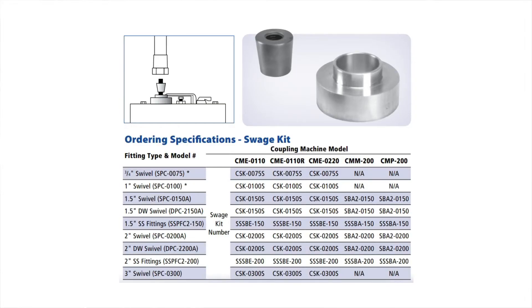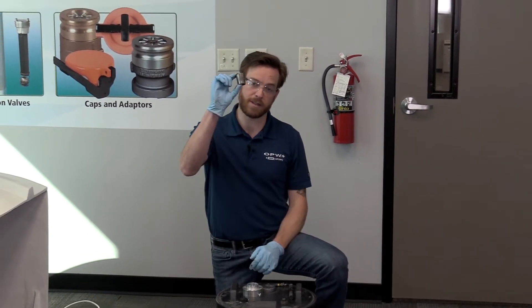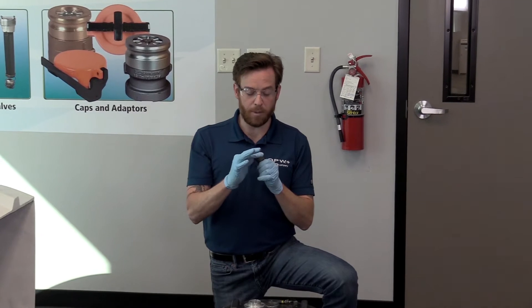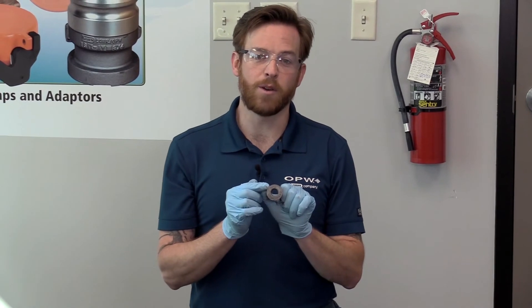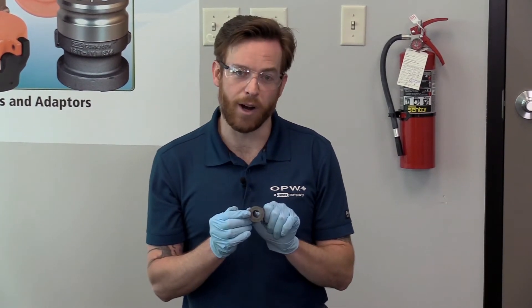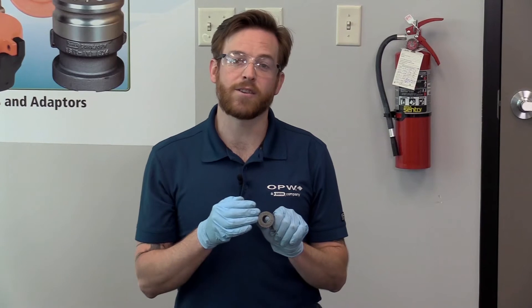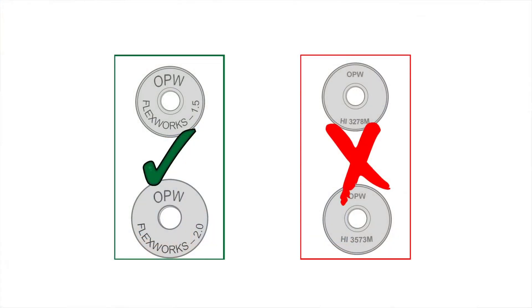First we'll look at the components in the CSK kits — these are the swedge block kits that you order to go with the swedge machine. In this kit you're going to have the actual swedge block itself; this is the mandrel that's going to be pulled through the fitting. It's very important to note before you swedge: look at the top of this. The version I have here says OPW FlexWorks 1.0. There's also FlexWorks 2.0 or FlexWorks 3.0 for those different sizes of pipe, and a 2R as well. If your swedge block says HI or has an HI part number, set that aside or discard it — that is for the Pisces system, which is no longer being sold.